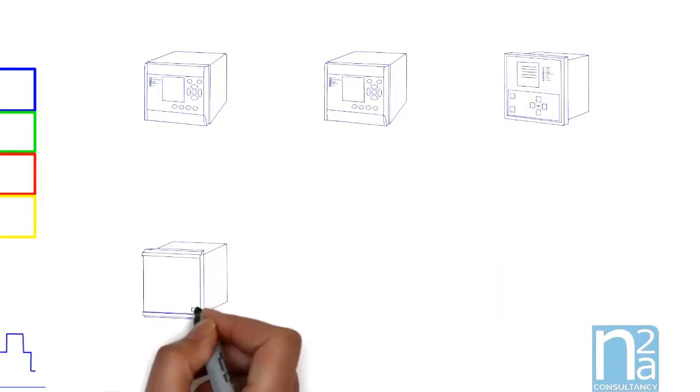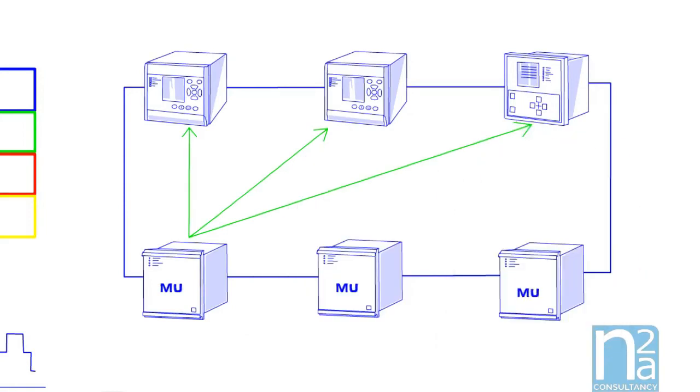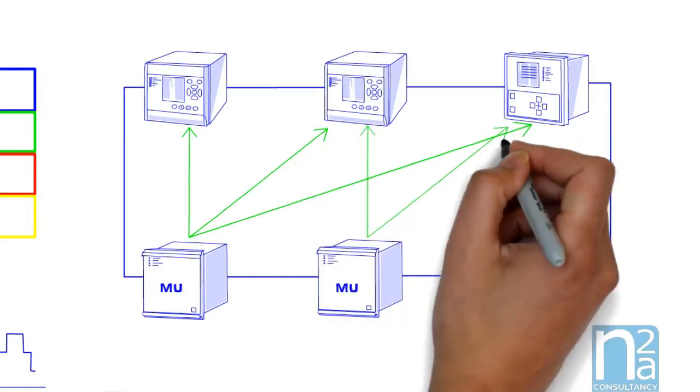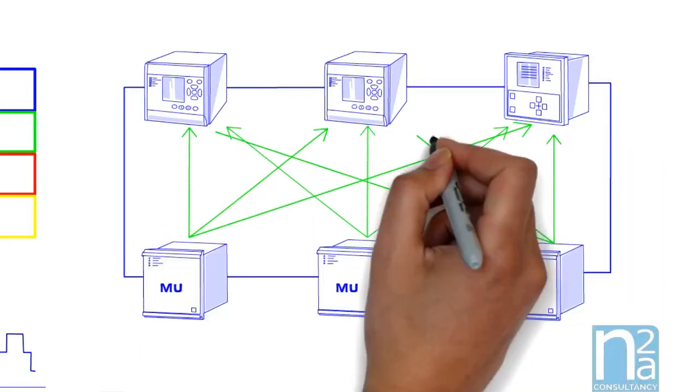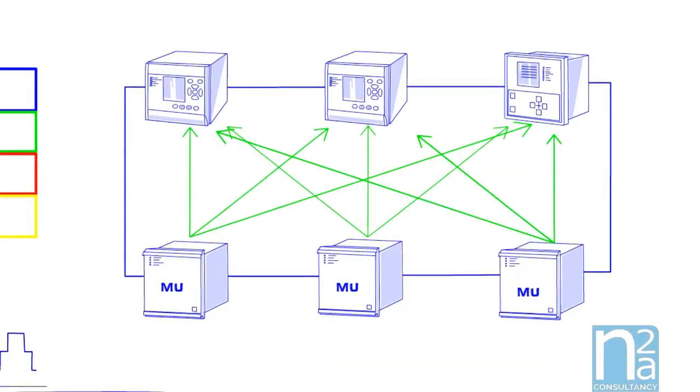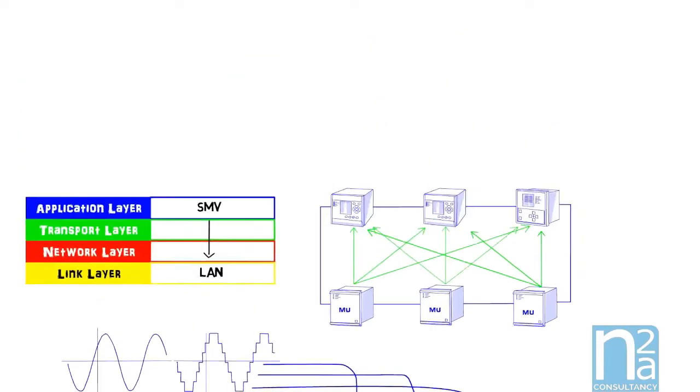This voltage and current measurement could be used by any IEDs which need the information, and this without additional wiring, just by using the process bus which needs to have sufficient bandwidth to support this large flow of information. In medium voltage applications, because of physical proximity between the relay and the switchgear, it is not much used today. But the possibility to share values of voltage and current and the absence of copper wires in the medium voltage compartment could be an advantage.